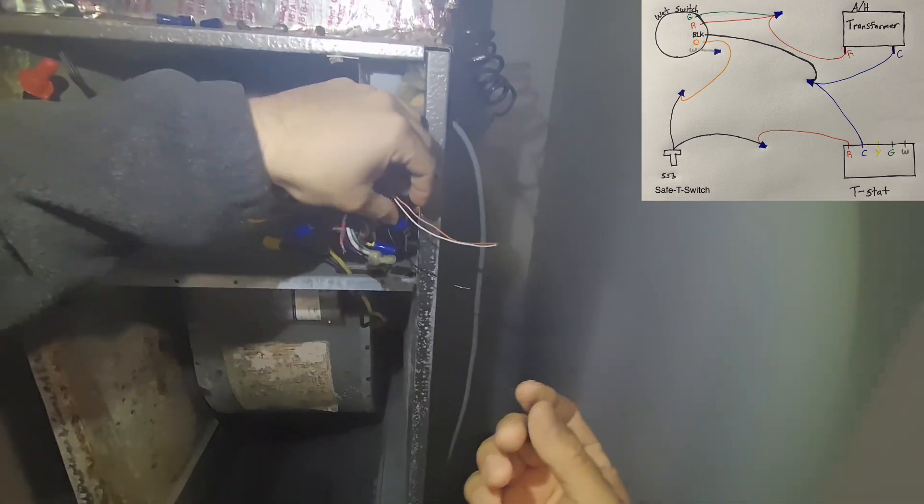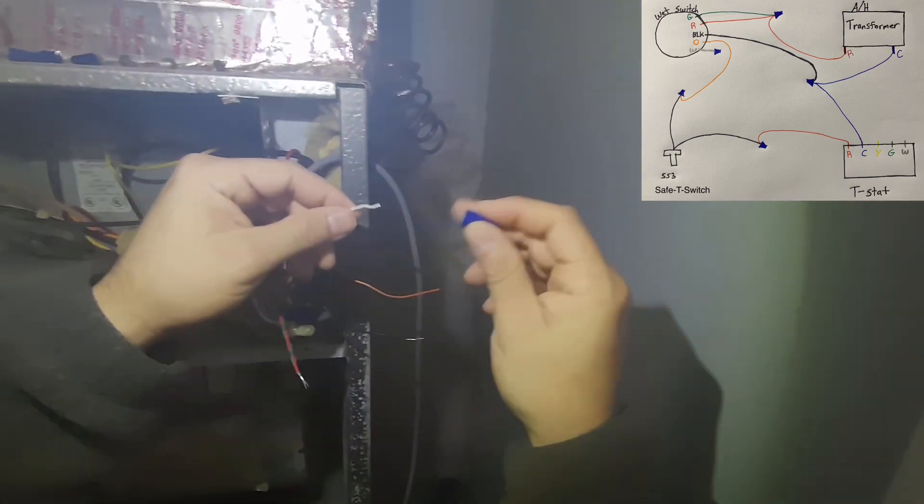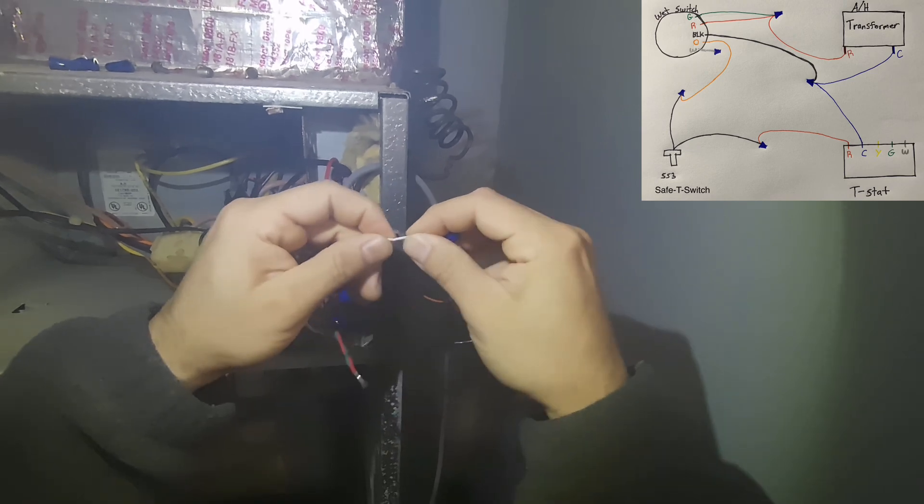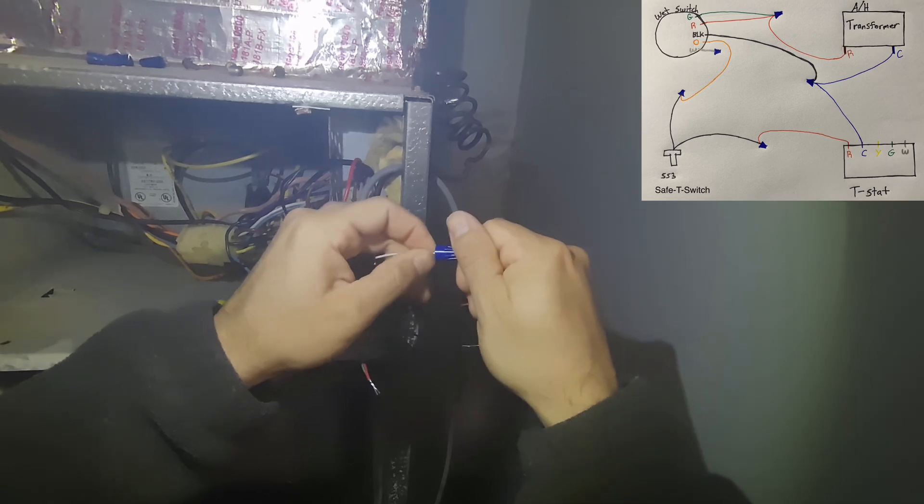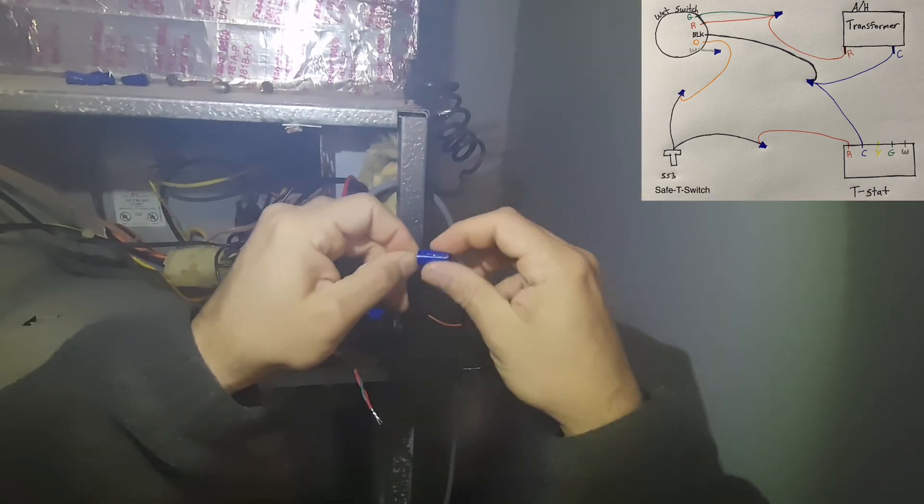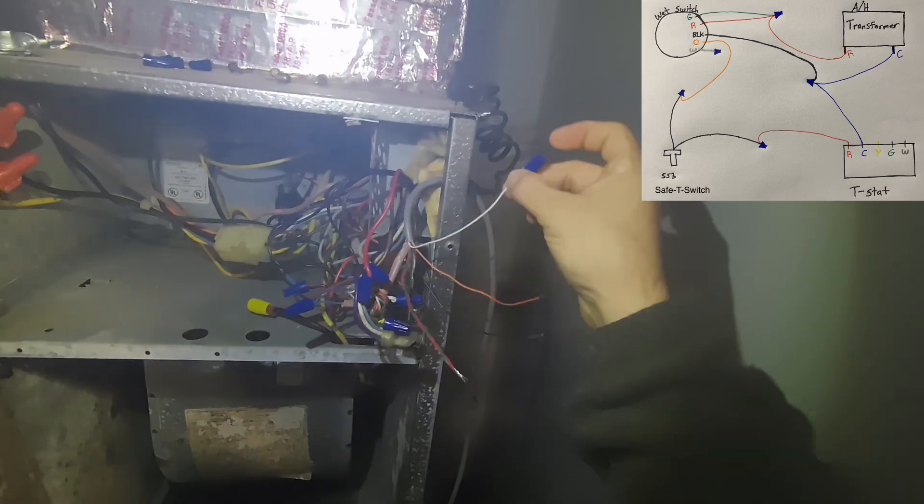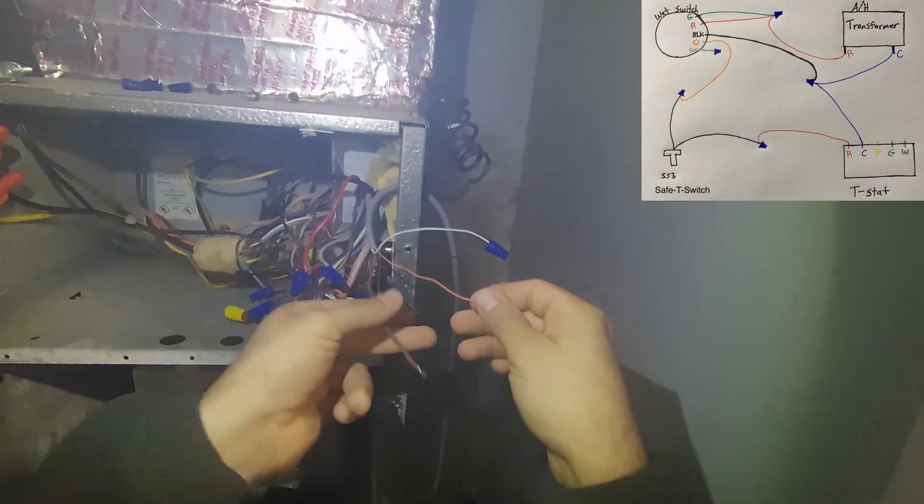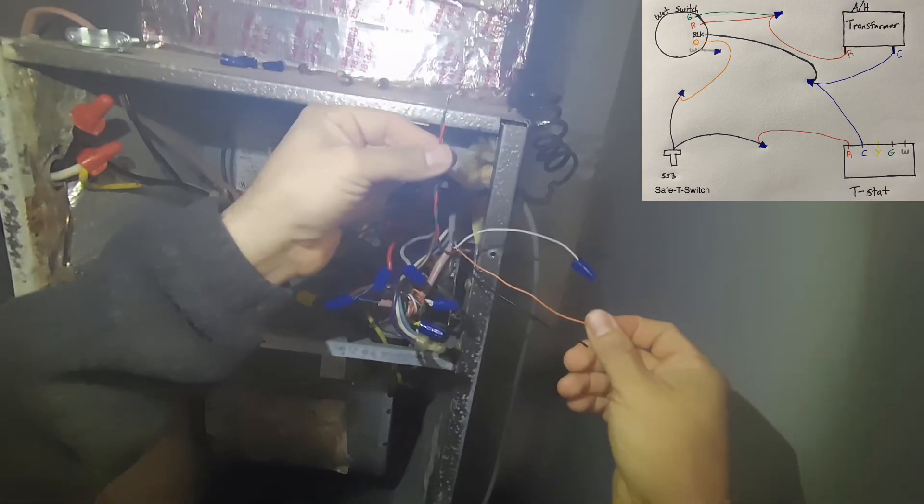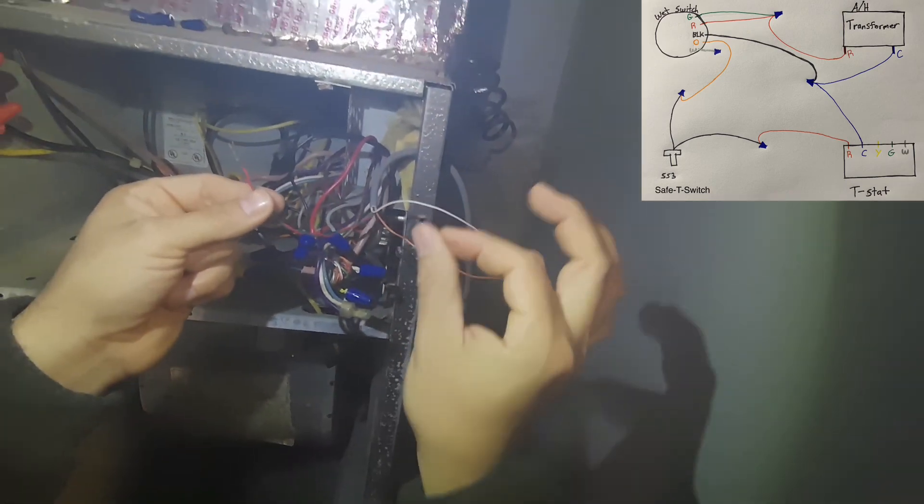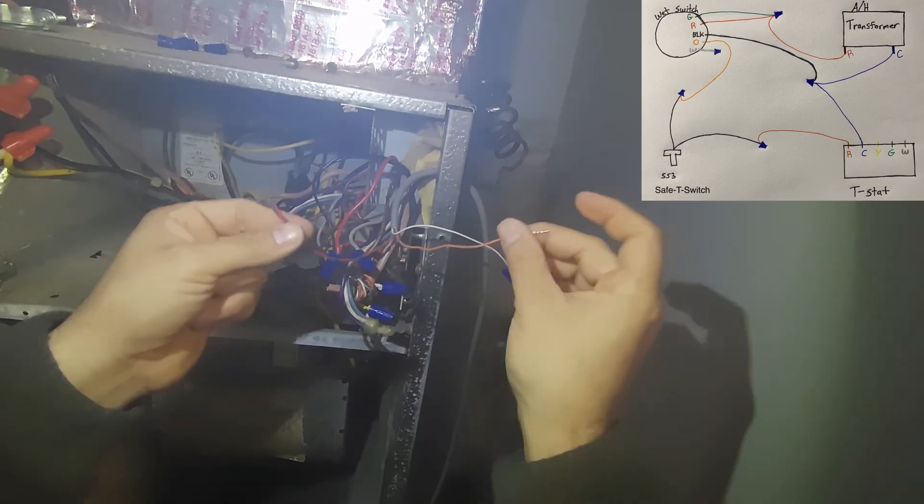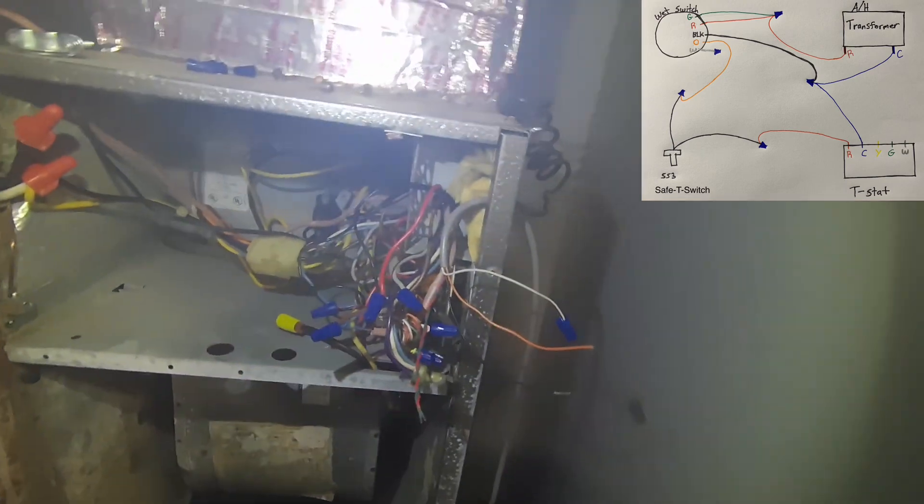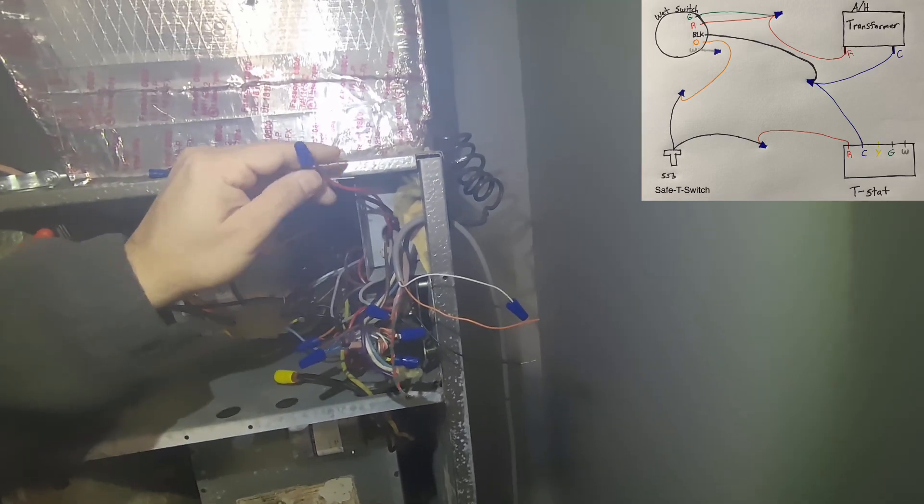You pretty much just cut the white one because your white is basically for like an alarm setup, which you don't have to worry about that if you're just installing it on an air handler unit for water detection at this moment. So we'll cap that off, don't worry about the white. Now we have our red and green which are going to be wired together, our orange, and then our black. This is your common, this is your power, and this is going to be the other side of your switch. So this goes to the other red side. You'll see in the diagram your air handler, our power is going to be this one right here.